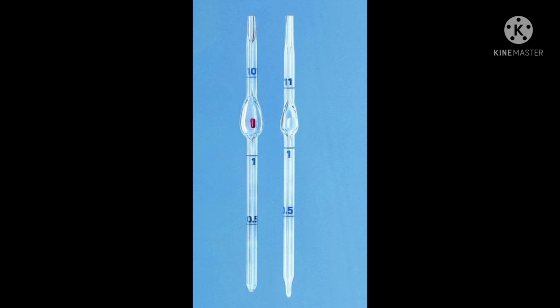The Thoma pipette is one of the instruments included in the hemocytometer set package. There are two types of Thoma pipette, with a difference in the glass grain in the pipette bulb. The Thoma pipette with red granules is the Thoma pipette for erythrocytes, while the white is the Thoma pipette for leukocytes. In addition to the glass grains, the dilution numbers are also different. At the end, the red color ends with the number 101, while the white color ends with 11. However, these numbers are not absolute volumes, but the most important thing is the volume ratio, which is the dilution that occurs in the pipette.